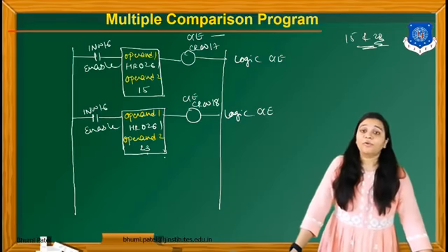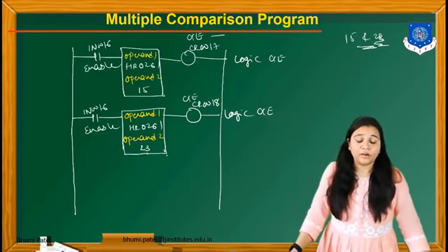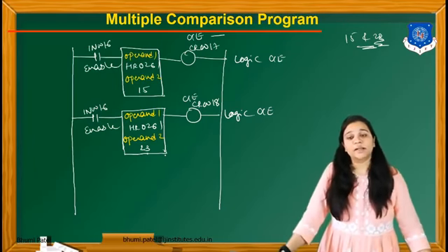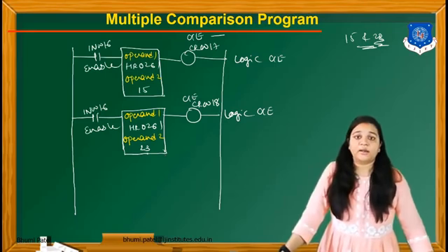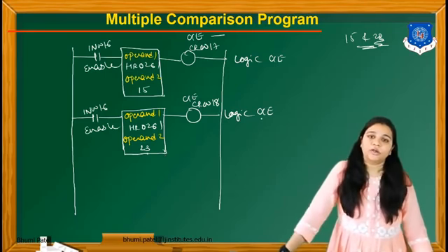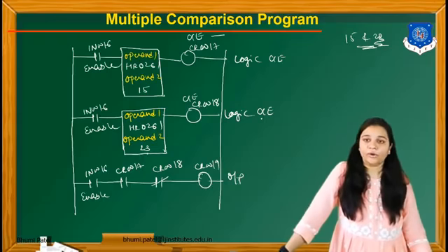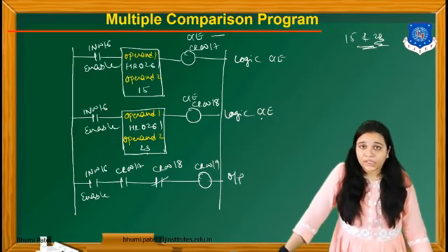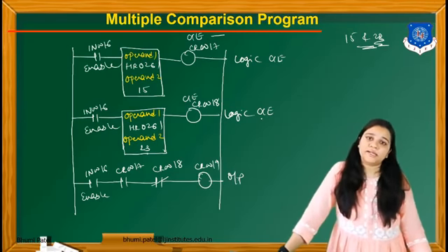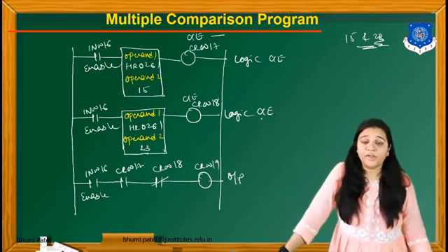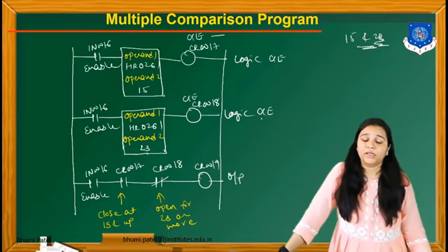You have to remember that in operand number 1 you take the same register, and the name of the input is also the same. Again we use the greater than or equal to function. This is the logic behind this program. The enable pin must be on. At that time, if my output 1, CR0017, is on and CR0018 is off, then we get the indicator on.